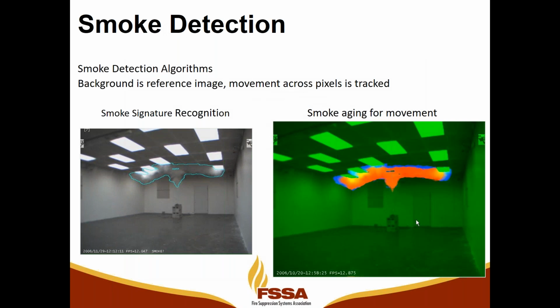The way that video analytics analyzes for smoke is, if you look at the left-hand screen, analytics are monitoring the image 15 frames a second and looking for an organized group of pixels having a light level change, moving in an organized pattern consistent with learned smoke algorithms. Now, we do that by tracking the amount of time the pixels are affected. On the right-hand image, you see the orange represents pixels that have been affected the longest. They're closer to the fire. The blue pixels represent pixels that have been newly affected and farther away from the fire. So, tracking the amount of time the pixels are affected.